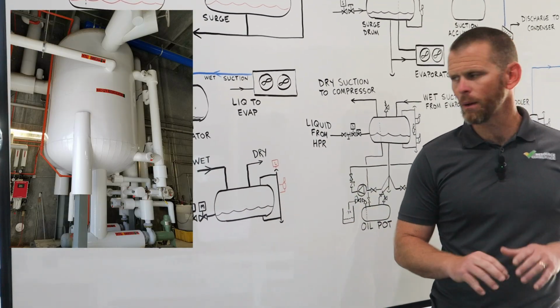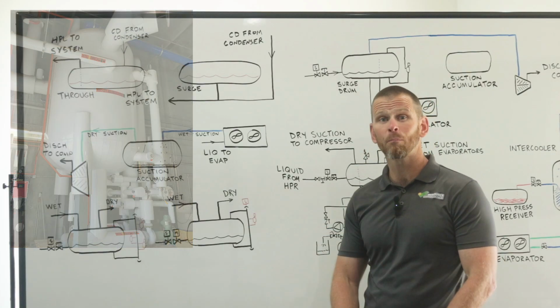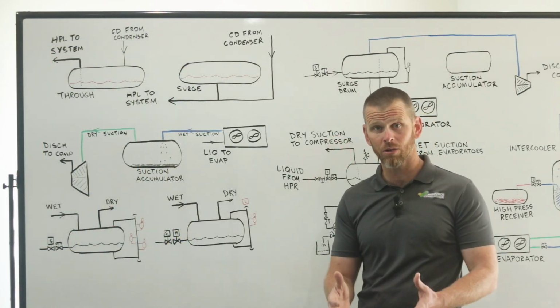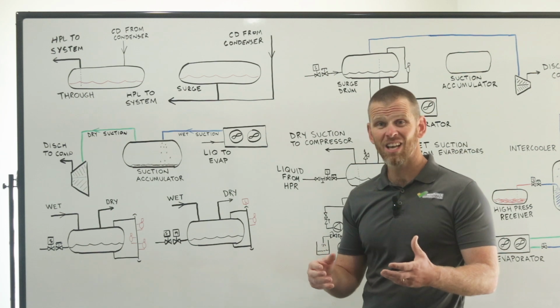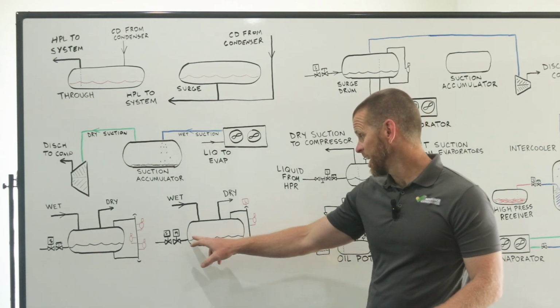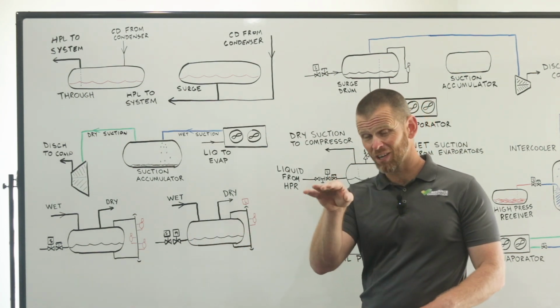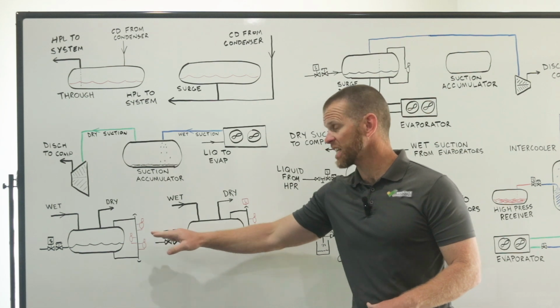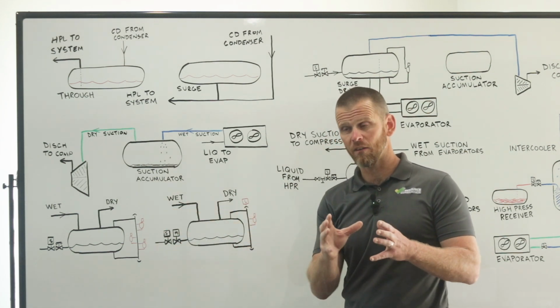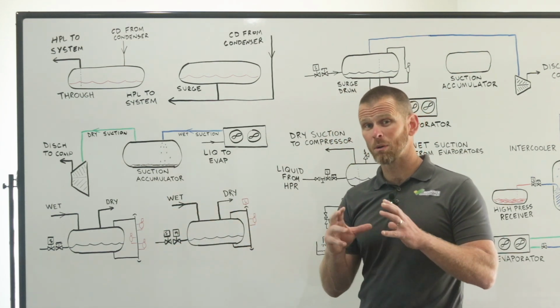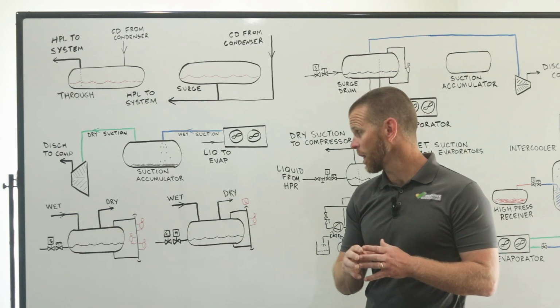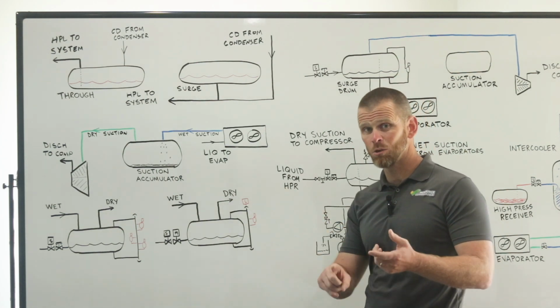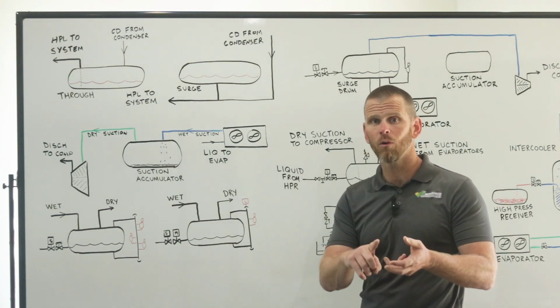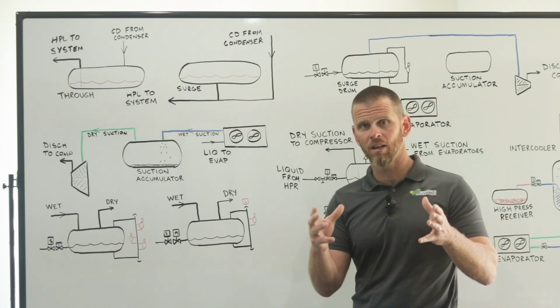There is a float, and we'll talk about that. But this level probe now provides continuous level monitoring and interlock capabilities. So we're able to more precisely control our level based on a specific percentage instead of just at fixed intervals like you have with a float tree. So that provides more precise control of your recirculator level. And this probe provides you with your operating level, your low level, and your high level all in one component.